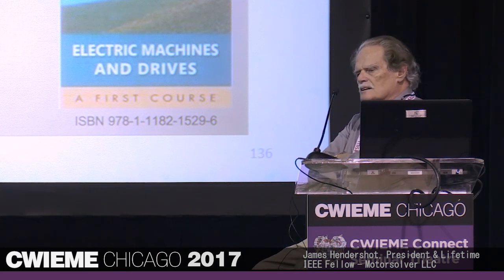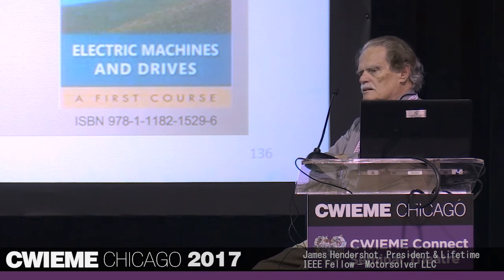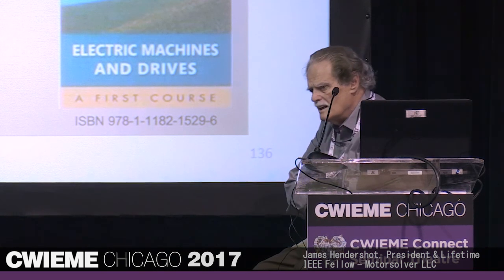Is this a tiny little motor? Yes, it is very, very tiny. It's a 50-60 watt motor. What eccentricity do you expect you have? 10,000ths. Oh, my gosh. That's an awful lot on that small of a motor. Ball bearings or sleeve bearings? No, it's plastic PPS material bearings. It's what? PPS.